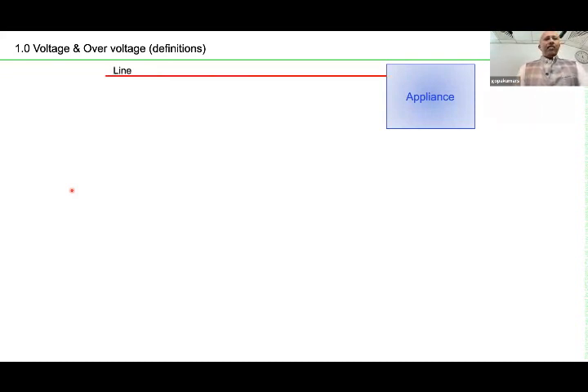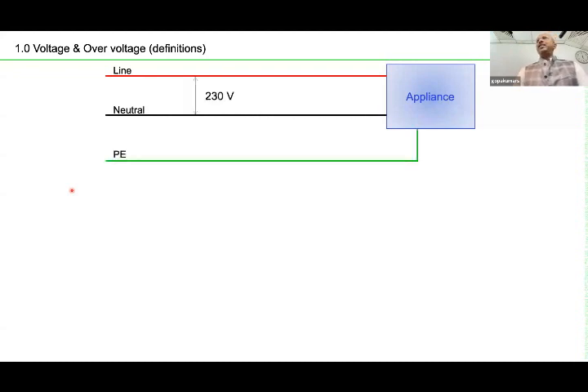Now, first of all, about the definitions explained in the standards. Sometimes, from country to country, there are some differences. Please excuse me, I am just trying to explain what is there in the standard. So 230 volt, I am just showing an appliance and a line, neutral, and a PE conductor. 230 is the nominal voltage. So under nominal voltage, all your equipment is safe. Nothing happens.